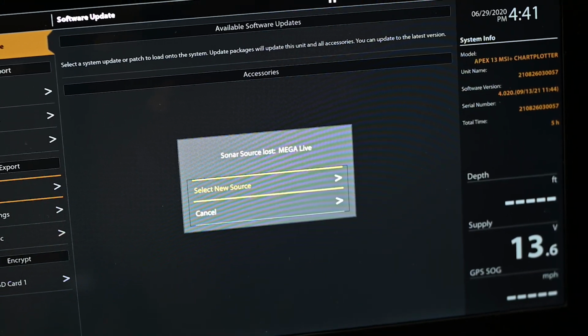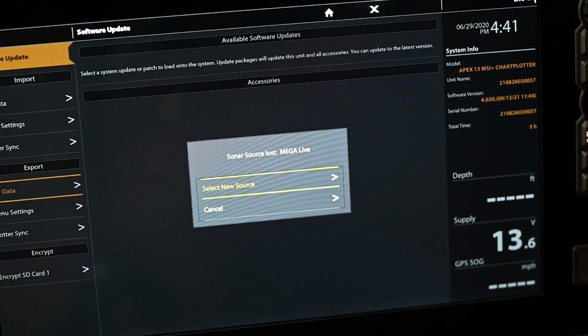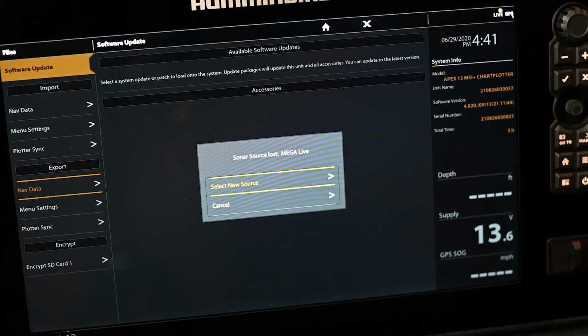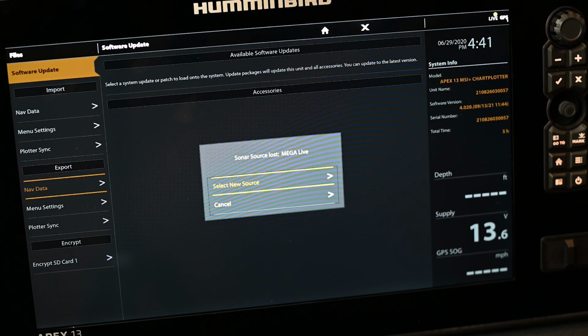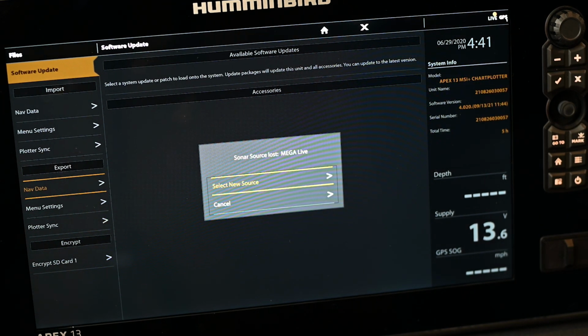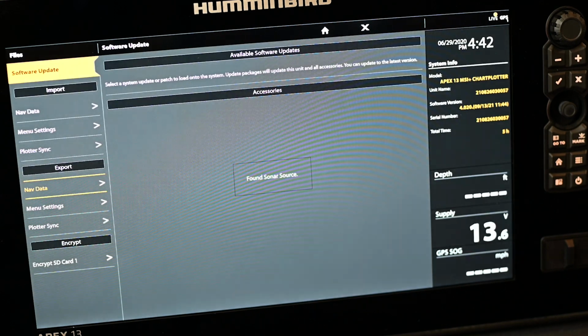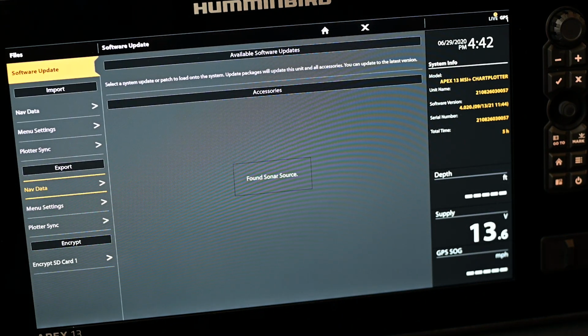It is very important that you do not pull the SD card out or disconnect the power to the control head, Ethernet switch, or MEGA Live transducer. Doing so may interrupt the update process and require service to your MEGA Live transducer. Once the unit reboots, the MEGA Live transducer should reconnect with the new firmware version installed.